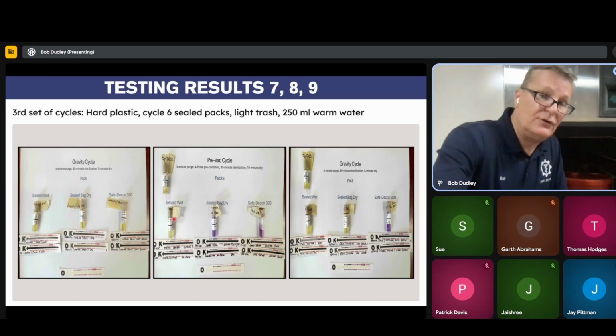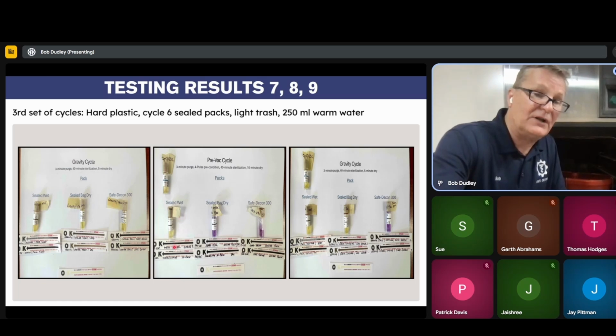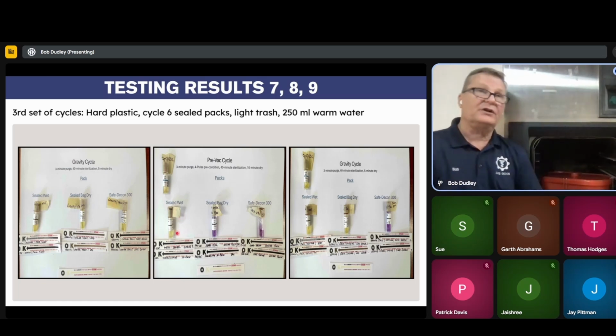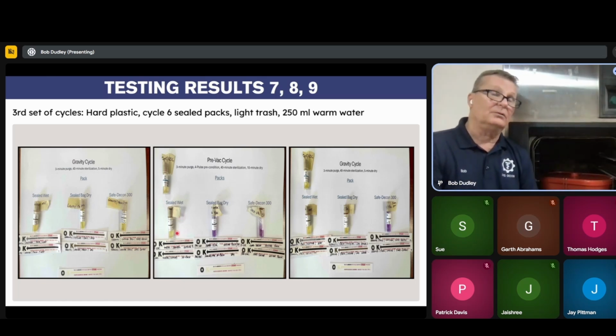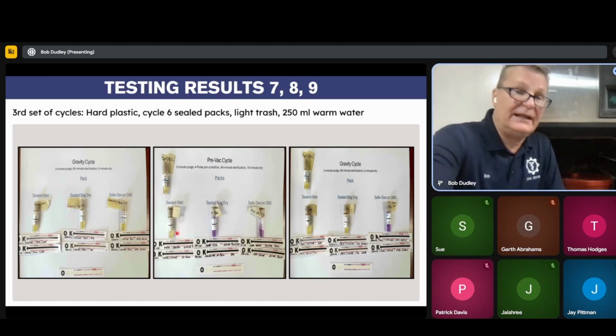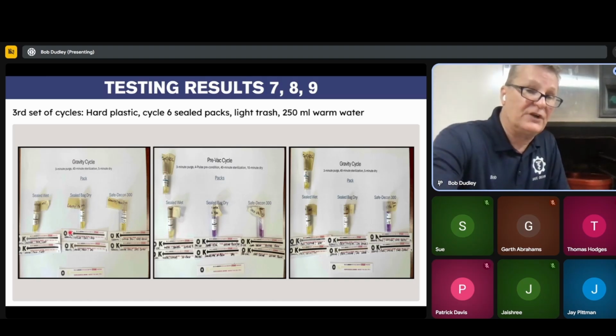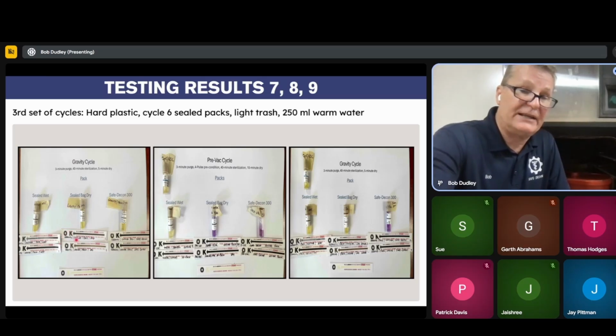But as you'll realize here, this is not producing steam inside the bag. If you remember the physics I just taught you in the thermodynamics, unfortunately that water is sitting there during the whole autoclave cycle until it gets to the end part, where it just opens up and releases that pressure. That's where you're probably getting the steam indication.